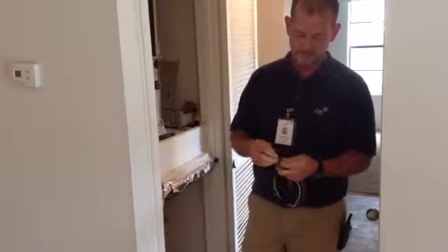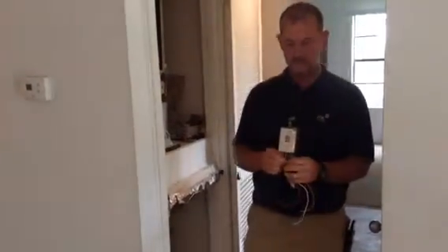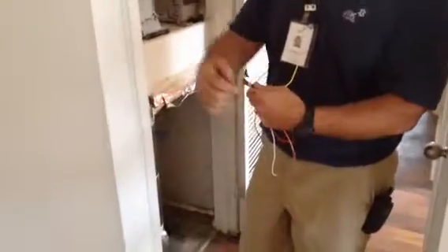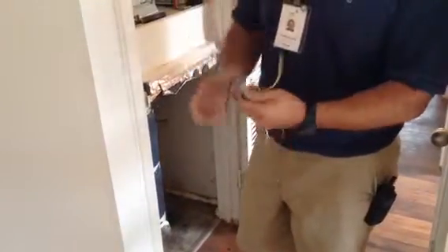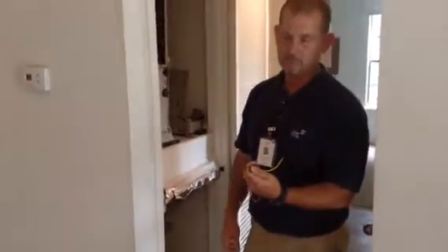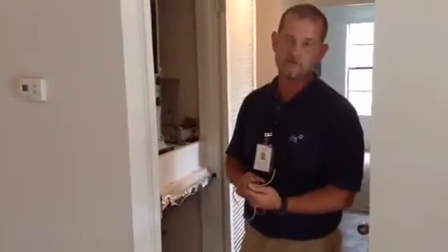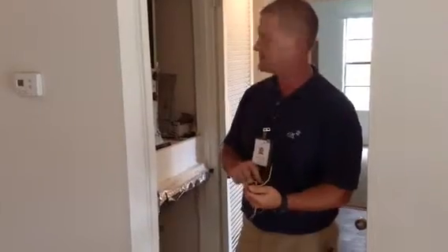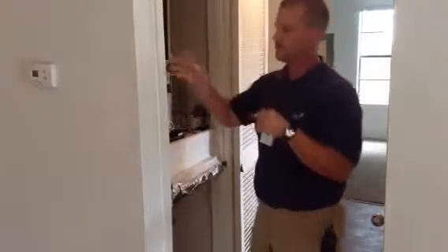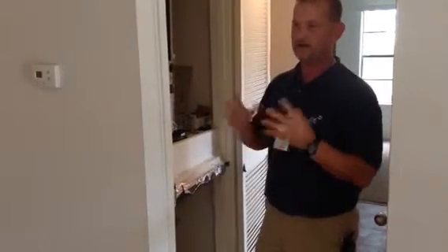Put one side on that side, one side on the other side. You're just going to get a spade and connect, hook it in there. Get some electrical tape and tape it up. There's your inline fuse. So it's going to blow that fuse before it blows the transformer again. It's a lot easier to change the fuse than it is to change the transformer. Once you get the transformer changed, it should give you voltage everywhere, and should be good to go.